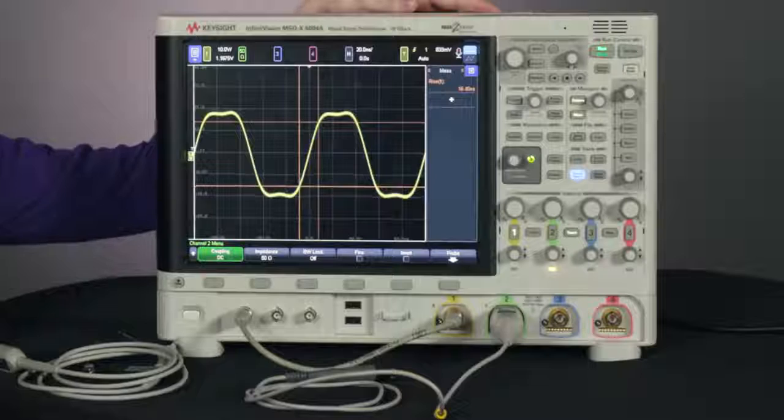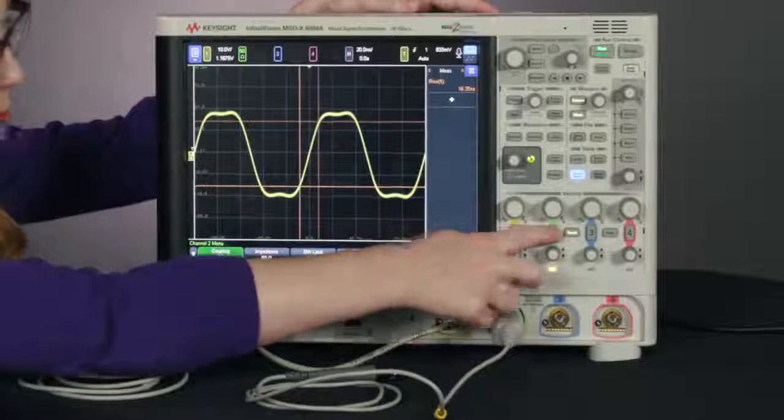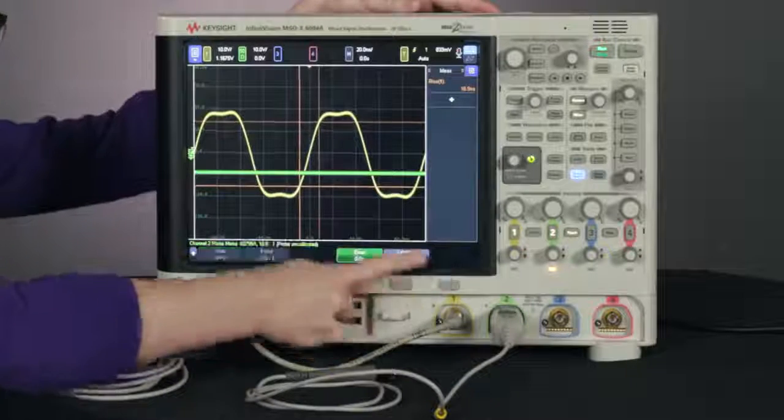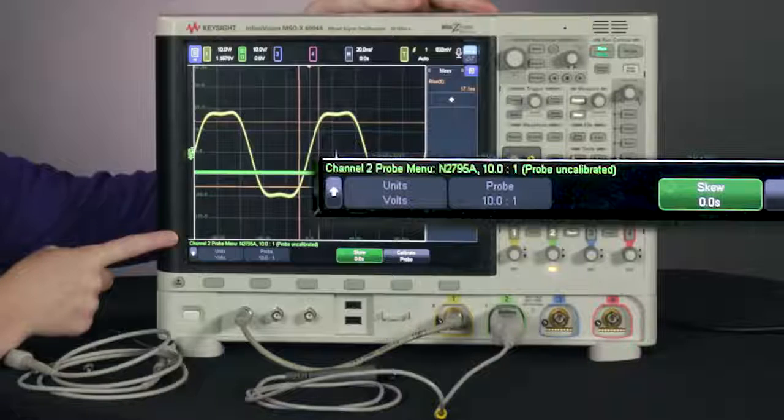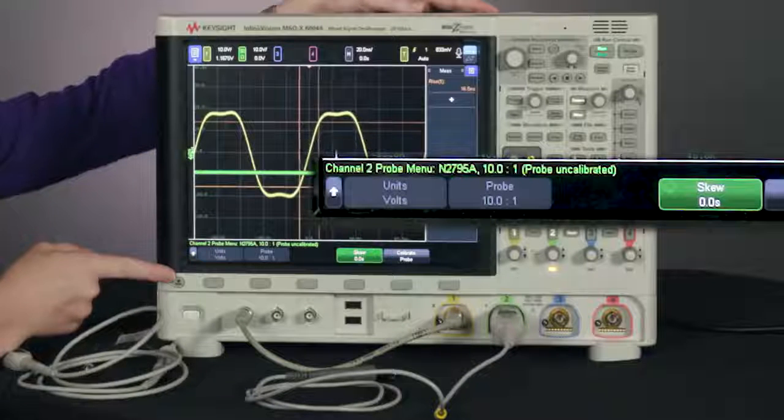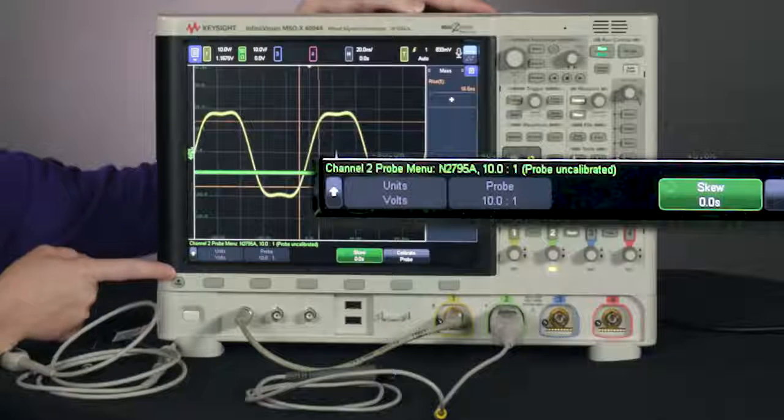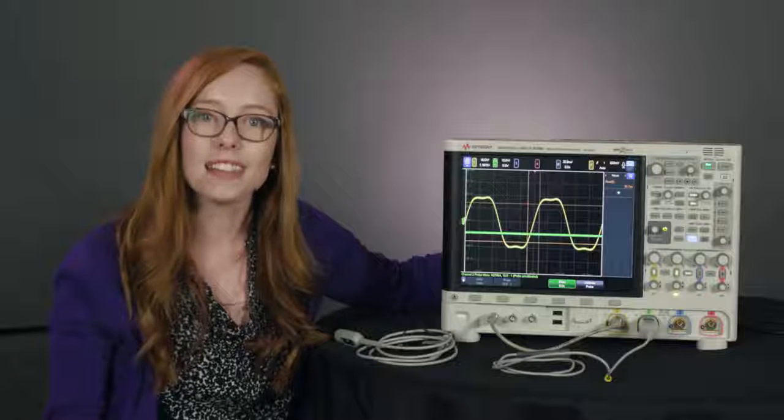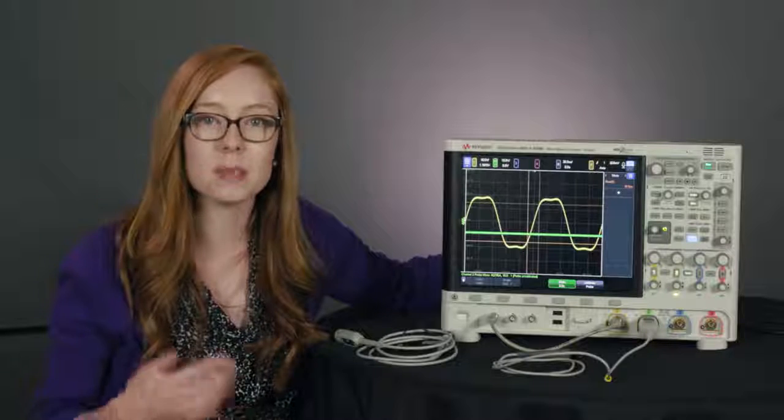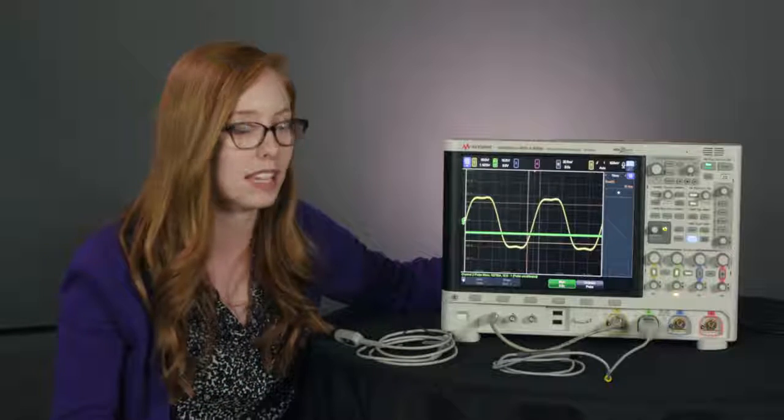And you can see this auto sensing capability when you plug in the active probe, turn on channel two and hit probe. You'll see the type of probe listed here with the attenuation factor and it's automatically detected the units in which the probe is measuring. And depending on the type of active probe there might be some other auto configuration that's done on the part of the oscilloscope as soon as the active probe is plugged in.